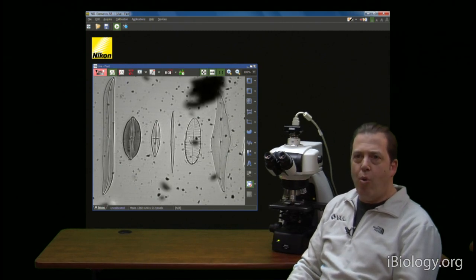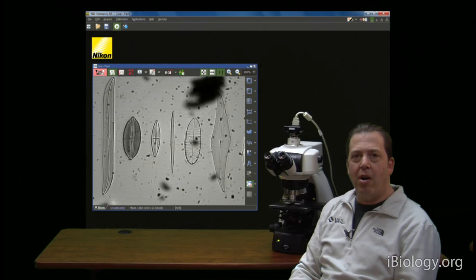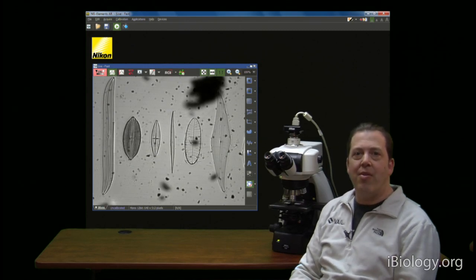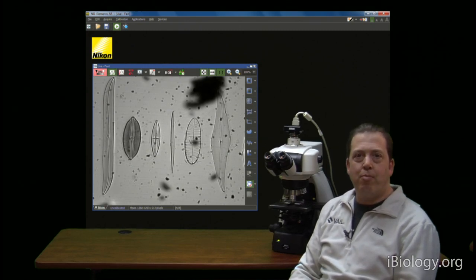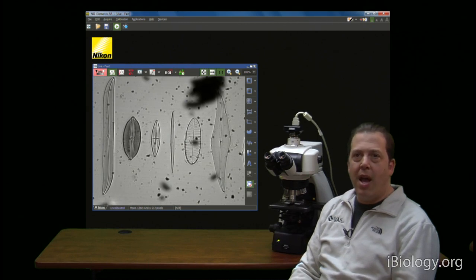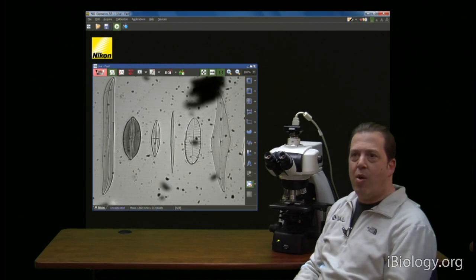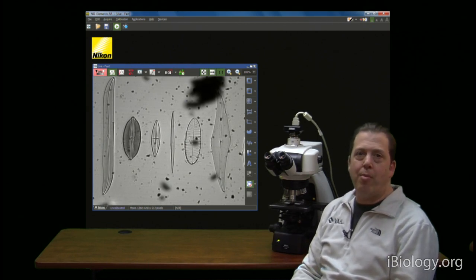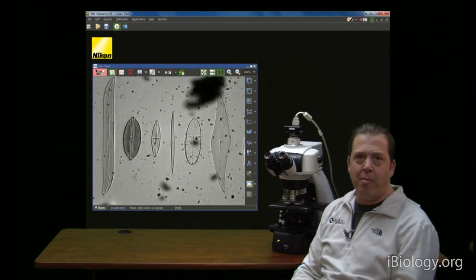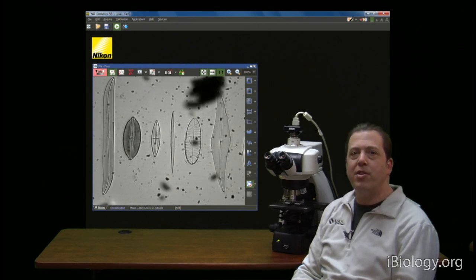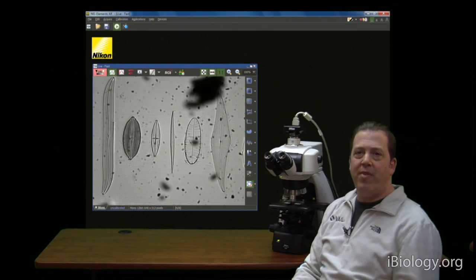So one of the first things you do in any type of imaging is to make sure in transmitted light that the microscope is in proper Köhler alignment. And what that's going to do is if you're not in proper alignment, the dirt that's in the aperture planes of the microscope that shouldn't normally be visible in the image planes will be visible.